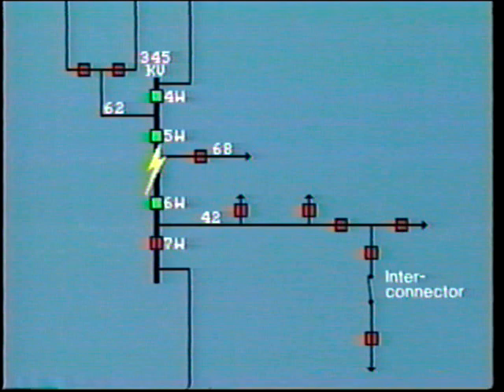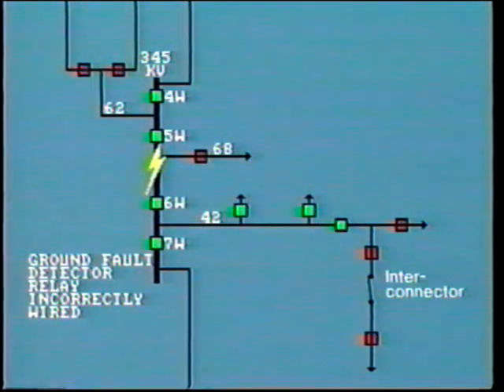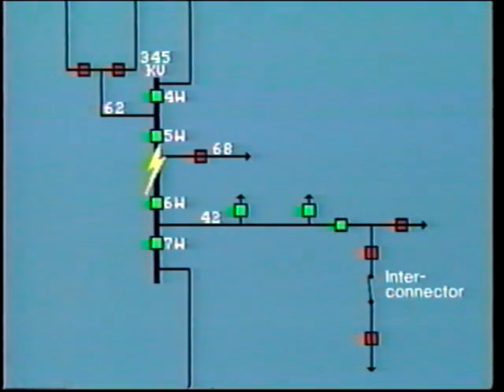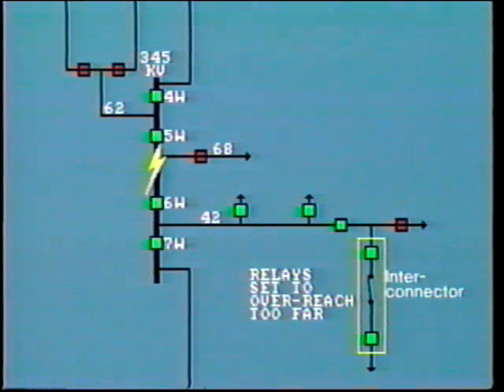Breaker 7W opened inadvertently, clearing line 42 and all associated breakers along the line due to transfer tripping. Once again, investigation showed that the ground fault detector relay at this point was incorrectly wired. There is more yet. As a result of the bus fault at Station A, this interconnector way out here tripped at both ends. Testing of the directional comparison relay system showed that the equipment was functioning correctly. However, it was determined that the relays in this scheme had been set to overreach too far. They have now been reset to a less sensitive value.